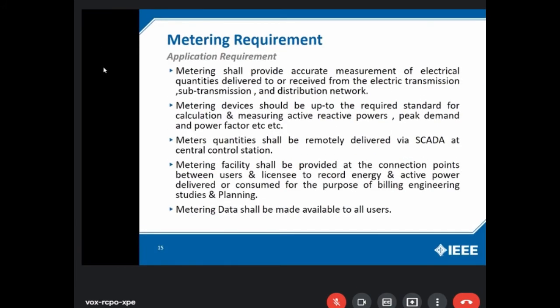Now the metering requirement. How we will implement and how we will exercise whatever the support requirements are. Metering shall provide accurate measurement of the electrical quantities delivered to or received from the electrical transmission substation, sub-transmission and distribution network. Metering devices should be up to the required standard for calculating and measuring active and reactive power, peak demand, power factor, etc.